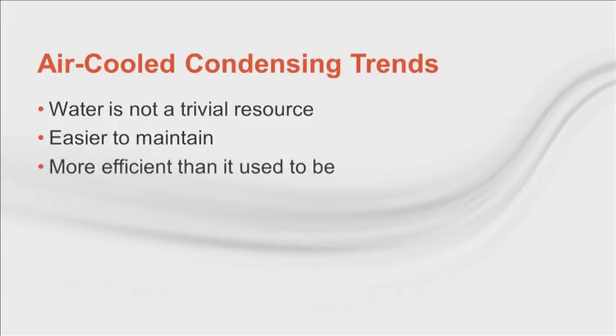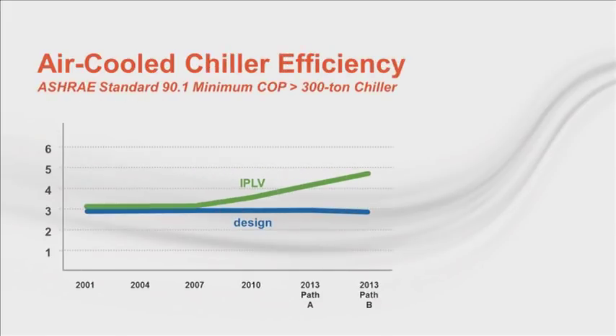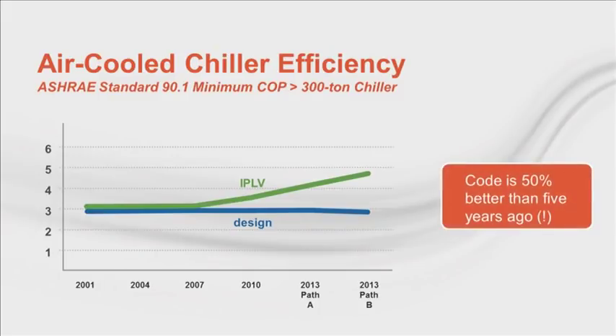Now let's talk about efficiency. The minimum code for new air-cooled chillers is 50% more efficient than it was just 5 years ago. An air-cooled chiller with a variable speed compressor, variable primary flow, and variable speed condenser fans is tough to beat. As in water-cooled, we have a split in 2013, introducing Path A and Path B for air-cooled chillers. We see that minimum chiller full load efficiency remains flat, but there are more efficient chillers that can be selected.